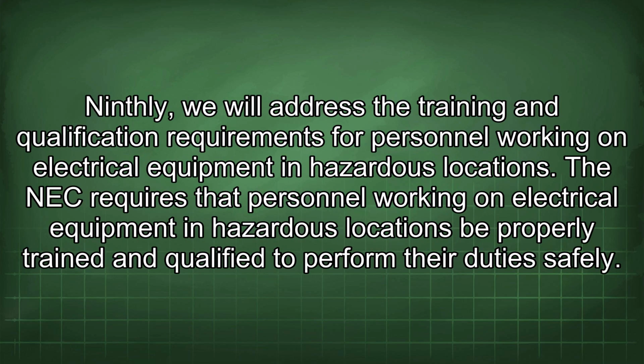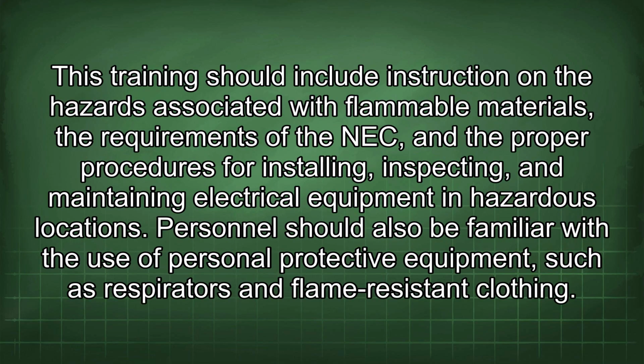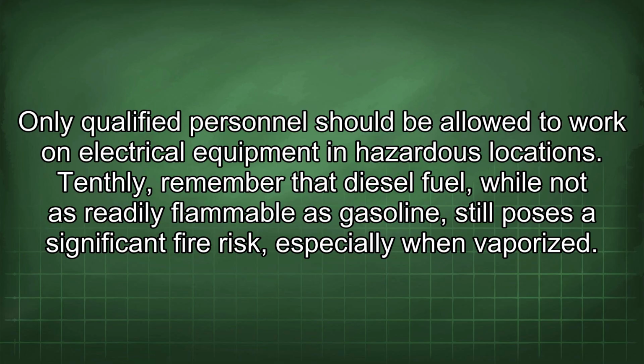Ninthly, we will address the training and qualification requirements for personnel working on electrical equipment in hazardous locations. The NEC requires that personnel working on electrical equipment in hazardous locations be properly trained and qualified to perform their duties safely. This training should include instruction on the hazards associated with flammable materials, the requirements of the NEC, and the proper procedures for installing, inspecting, and maintaining electrical equipment in hazardous locations. Personnel should also be familiar with the use of personal protective equipment, such as respirators and flame-resistant clothing. Only qualified personnel should be allowed to work on electrical equipment in hazardous locations.